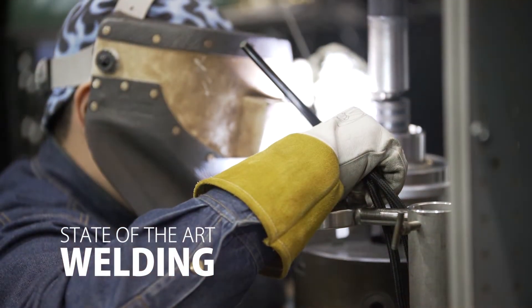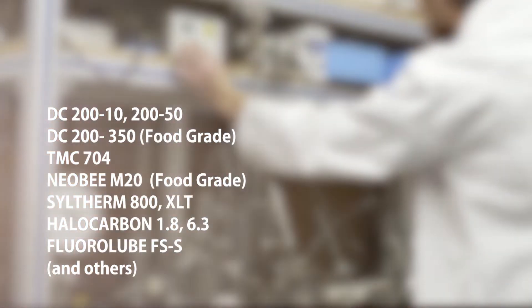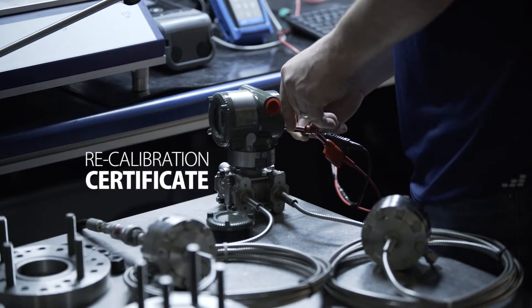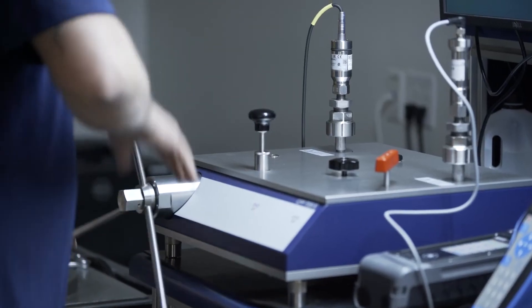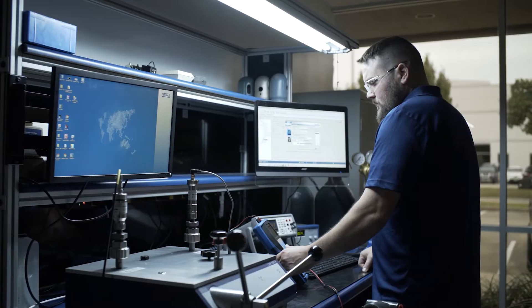The system is then reassembled using state-of-the-art welding capabilities and filled with the best fill fluid option for your application. Once the assembly is complete, all service diaphragm seal systems receive a recalibration with certificate. The WIKA lab can also conduct traceable calibration according to ISO 17025 of your field instruments with highest accuracy, up to maximum pressure.